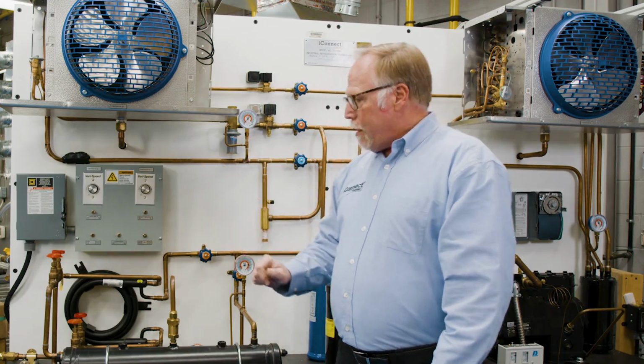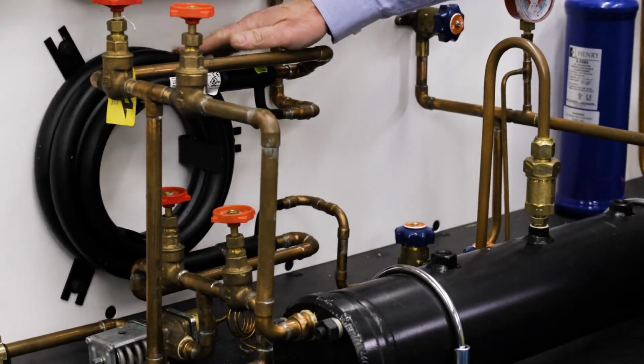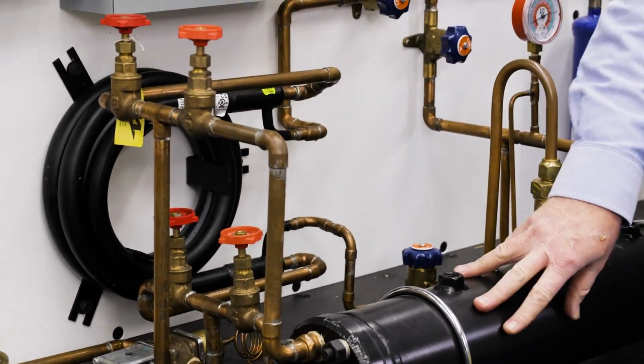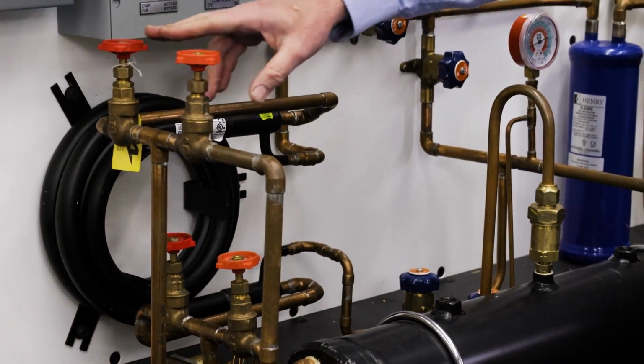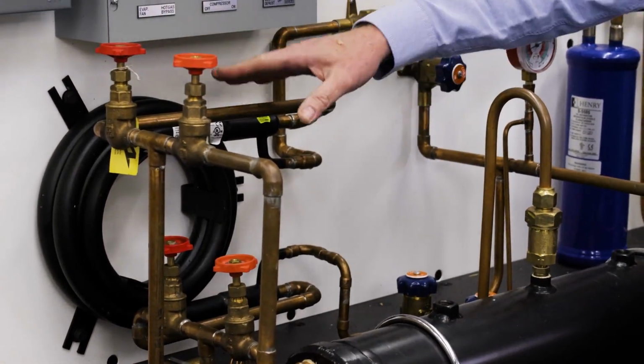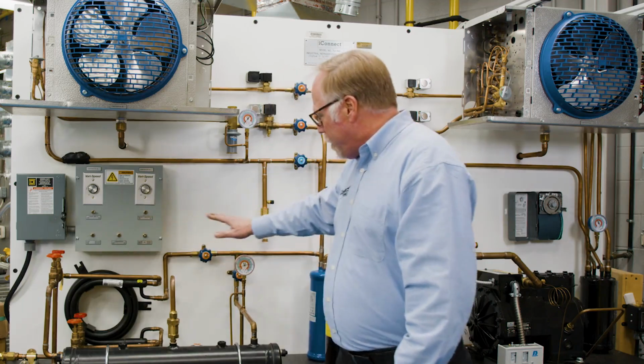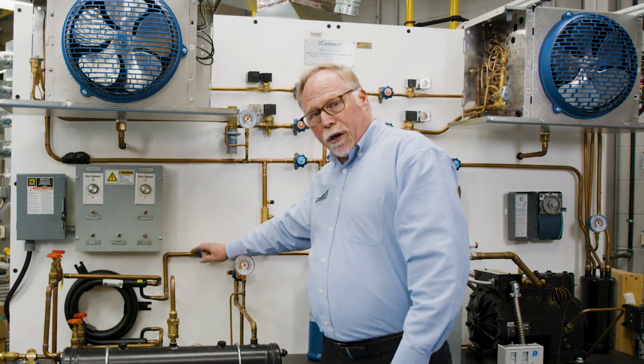Now the fourth lesson is going to be on the water side of this system. Remember, we have a coax coil here, and a tube and shell here. With these valves, you can route the water in either direction, but don't forget, you also need to reroute the discharge gas to whichever coil you're using.